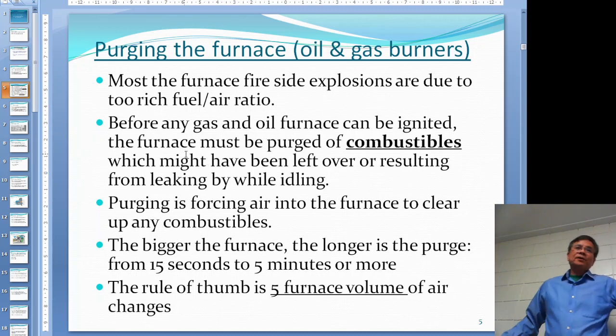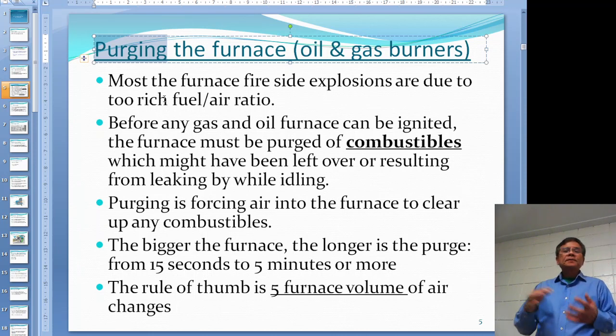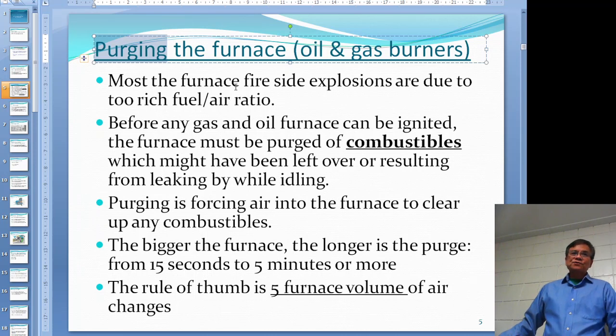This topic is quite important for burning: purging is very important for oil and gas burners. The reason why we purge the furnace is because if the mixture of fuel and air is not right - if you have a too-rich mixture of gas - you might have a furnace explosion. This is called the fire side, on the furnace side, not the water side. So before any gas or oil furnace can be ignited, you must purge the furnace of combustibles.